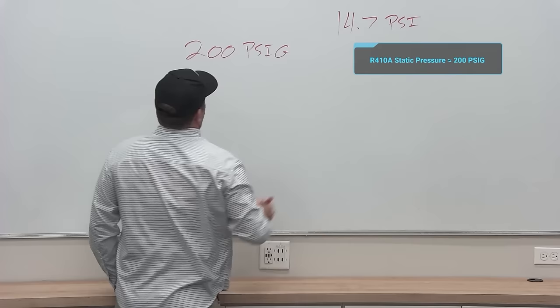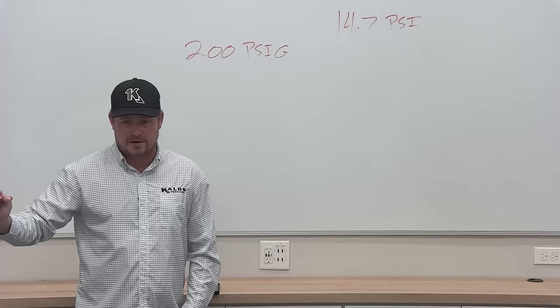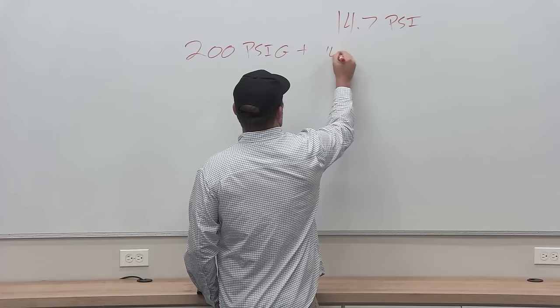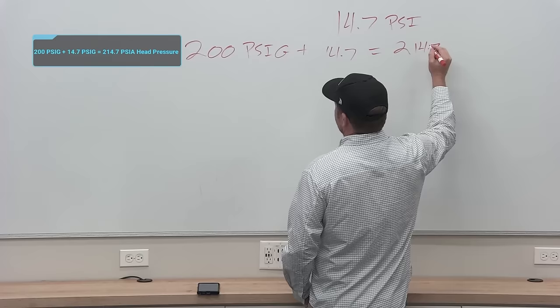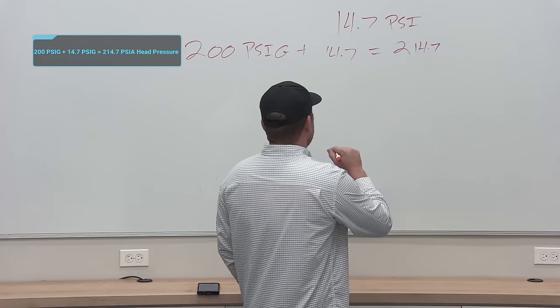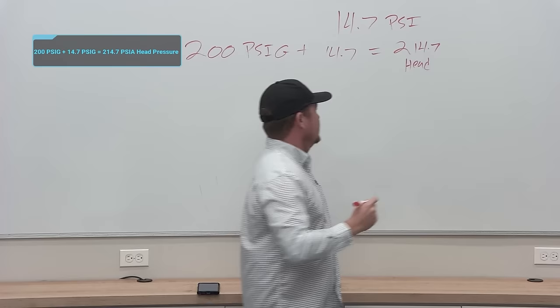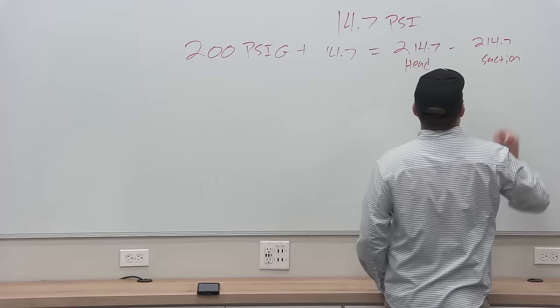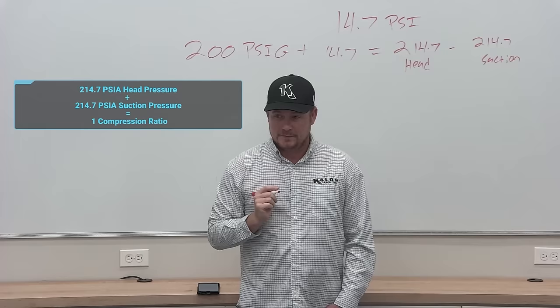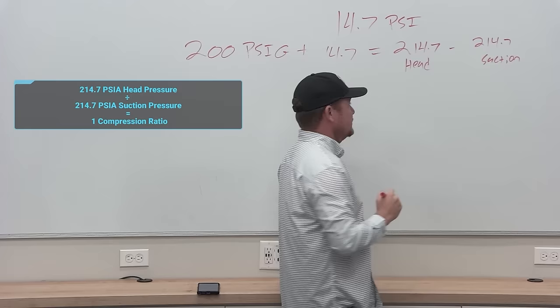That's 200 PSIG — pounds per square inch gauge — and that gauge pressure is zeroed at atmospheric pressure. To convert to absolute, you add 14.7, so 200 plus 14.7 equals 214.7 PSIA. If the system isn't running, both head and suction are 214.7 absolute. So 214.7 divided by 214.7 gives us a compression ratio of one.